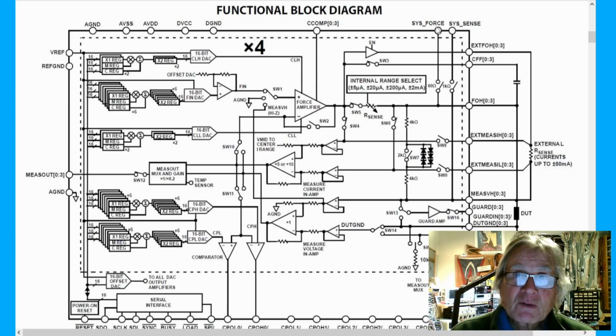So the way sysforce and syssense are typically used is that these will drive a multimeter or calibration hardware so that you can quickly calibrate all the channels within a system. There's only one sysforce and one syssense, and each channel has one of these switches, so these signals are common to all 4 channels.